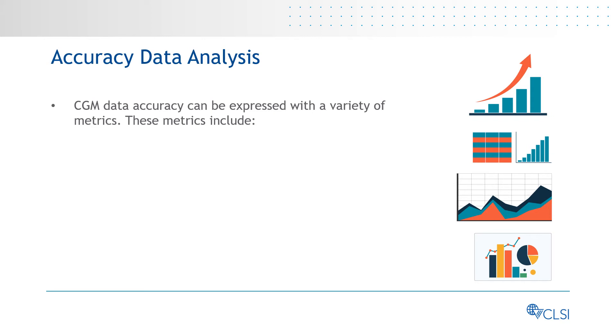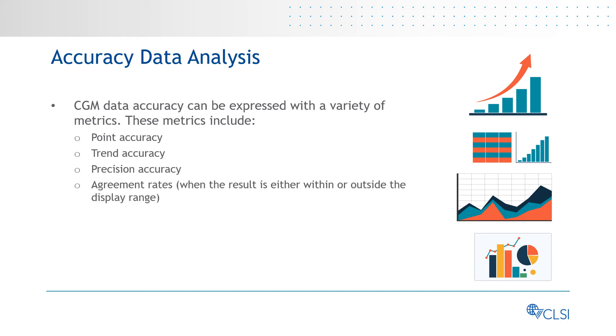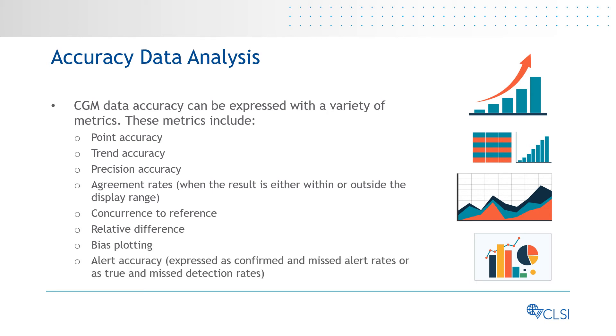CGM data accuracy can be expressed with a variety of metrics. These metrics include point accuracy, trend accuracy, precision accuracy, agreement rates when the result is either within or outside the display range, concurrence to reference, relative difference, bias plotting, and alert accuracy expressed as confirmed and missed alert rates or as true and missed detection rates.